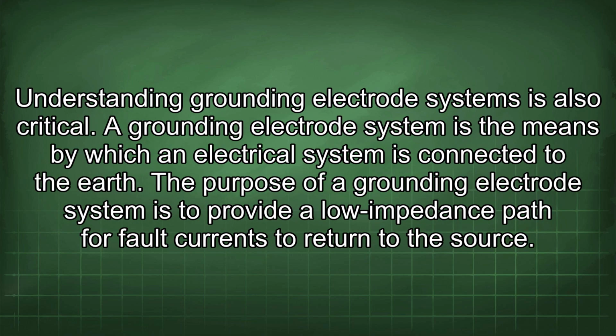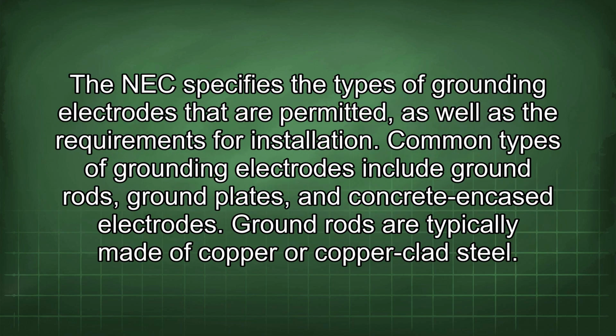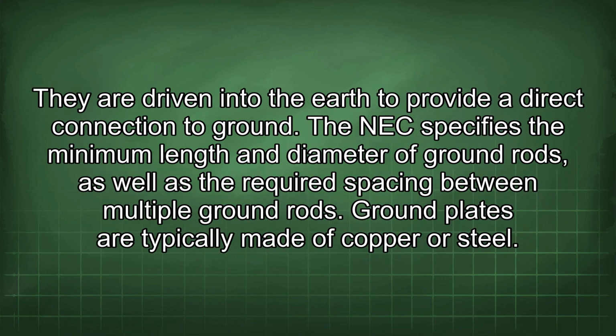Understanding grounding electrode systems is also critical. A grounding electrode system is a means by which an electrical system is connected to the earth. The purpose of a grounding electrode system is to provide a low impedance path for fault currents to return to the source. The NEC specifies the types of grounding electrodes that are permitted, as well as the requirements for installation. Common types of grounding electrodes include ground rods, ground plates, and concrete encased electrodes. Ground rods are typically made of copper or copper-clad steel. They are driven into the earth to provide a direct connection to ground.